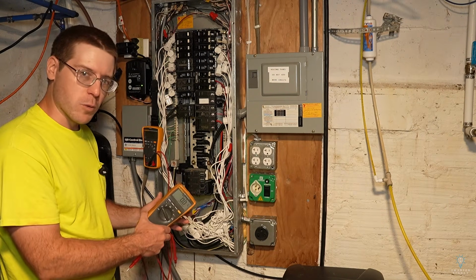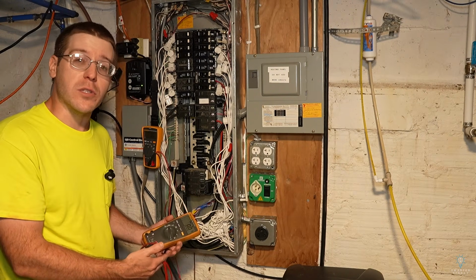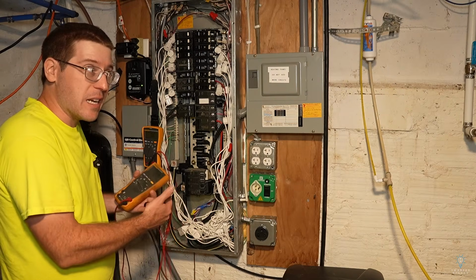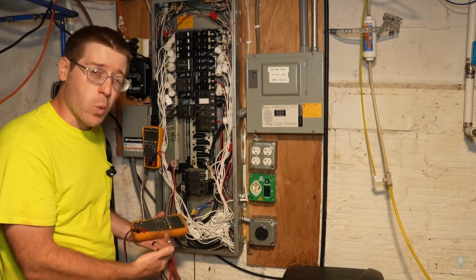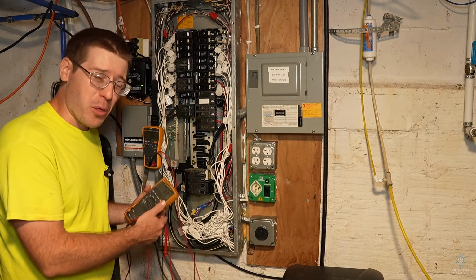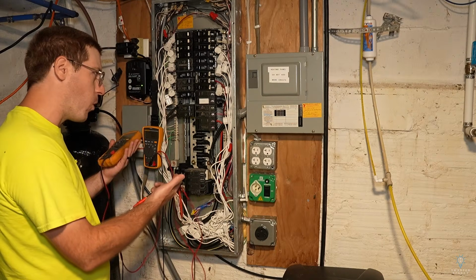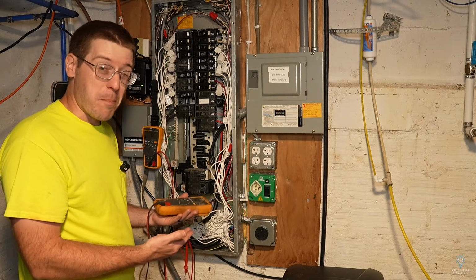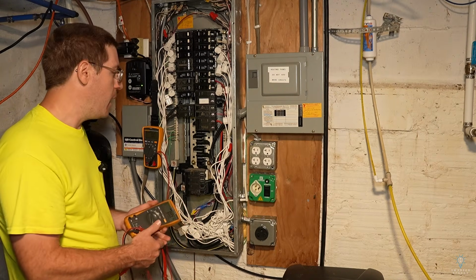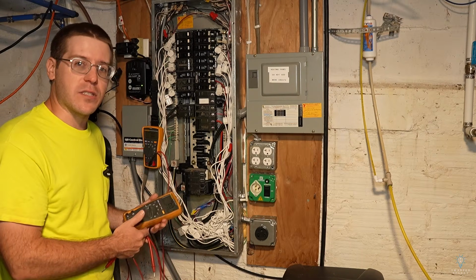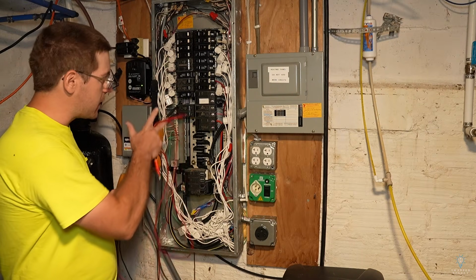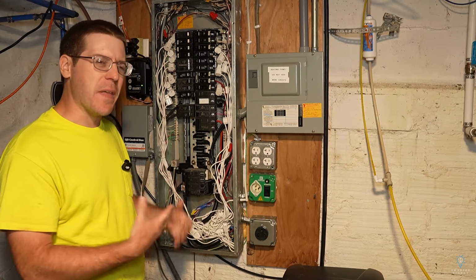We've fixed that neutral problem. There is always going to be voltage drop in any electrical system. It's just an inherent part of how wires work with electricity. We were seeing about a 30 volt spread before, and now we're only seeing about, what, a maximum of a 3 volt spread. So I would definitely say that solved the problem. I'm happy with this.